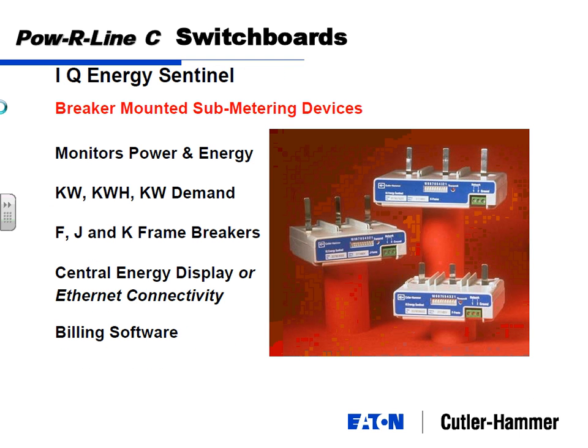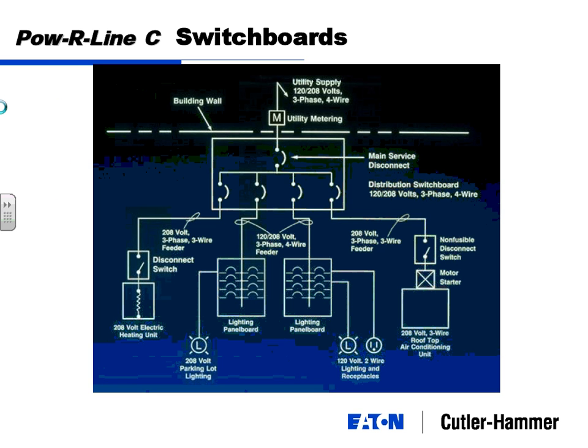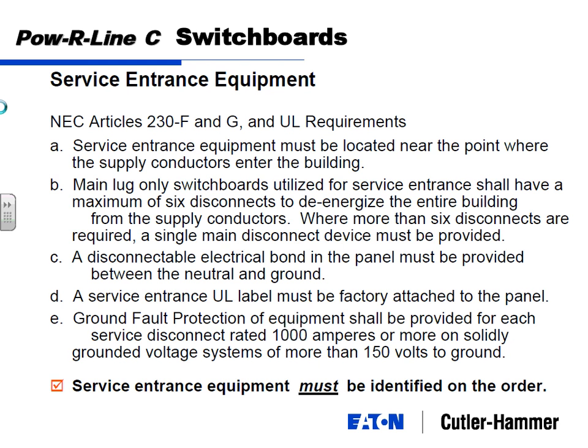Same type of energy metering devices, sub-energies. And we're going to touch just on service entrance a little bit. If you've got a building wall here, here's one that shows utility metering outside. Break through the building wall, and you've got your switchboard here. And this switchboard is classified as a service entrance switchboard because it's got a main service disconnect. It's the point where the service entrance equipment must be located, near the point where the supply conductors enter the building. You've got a couple of different configurations.